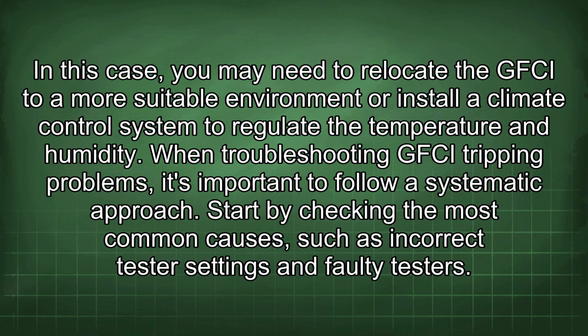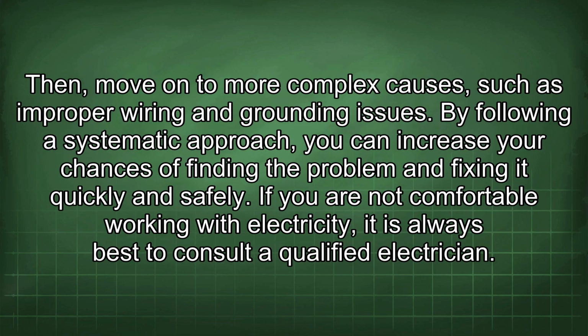When troubleshooting GFCI tripping problems, it's important to follow a systematic approach. Start by checking the most common causes, such as incorrect tester settings and faulty testers. Then, move on to more complex causes, such as improper wiring and grounding issues. By following a systematic approach, you can increase your chances of finding the problem and fixing it quickly and safely.